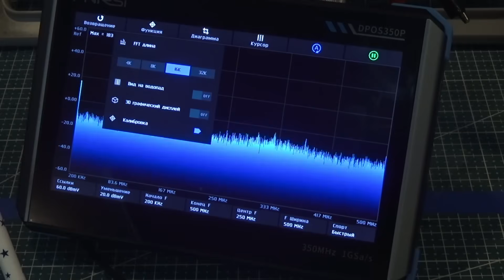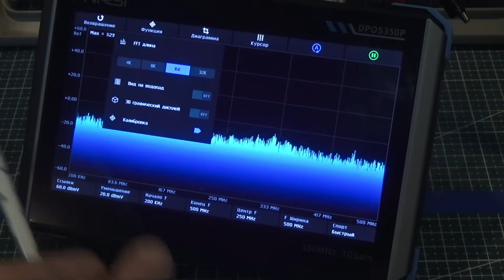What exactly is FFT length? FFT length is the number of points the device uses for analysis. The greater the length, the higher the frequency accuracy, meaning better resolution. You'll be able to see small peaks that are impossible to spot at lower resolutions. But the higher the resolution and the more points there are, the slower the readings will update. If you only need a basic, non-detailed analysis, you can lower the resolution and the device will work quickly and smoothly. A bit later, I'll show you what this looks like in practice.